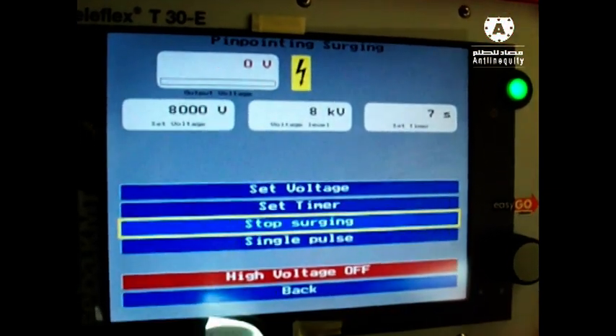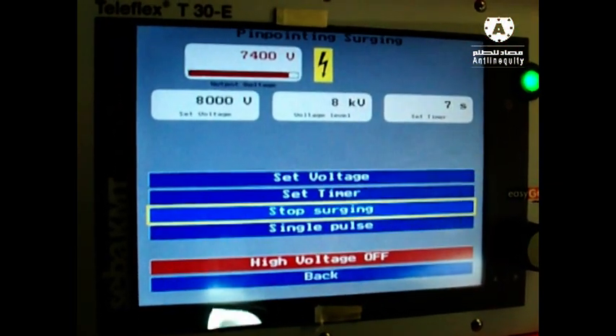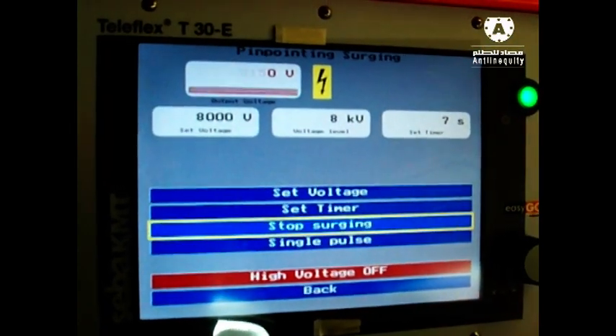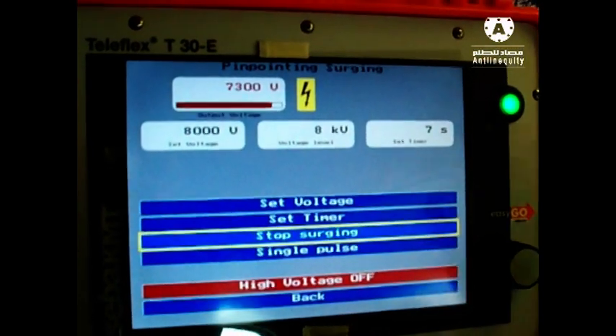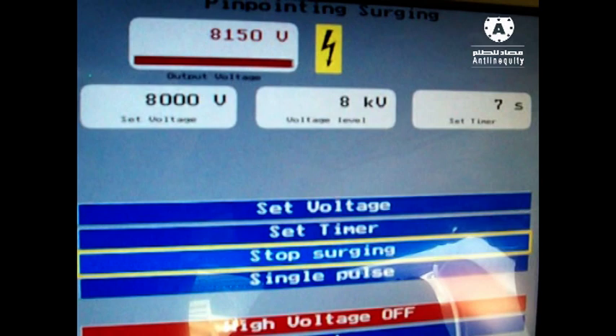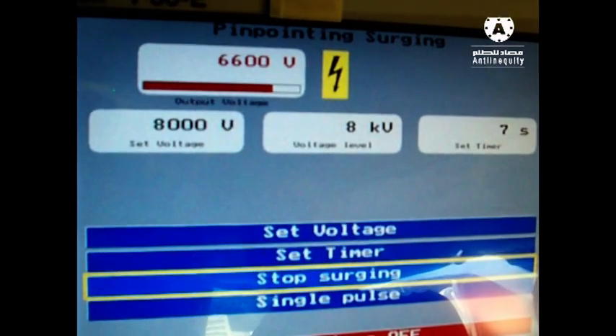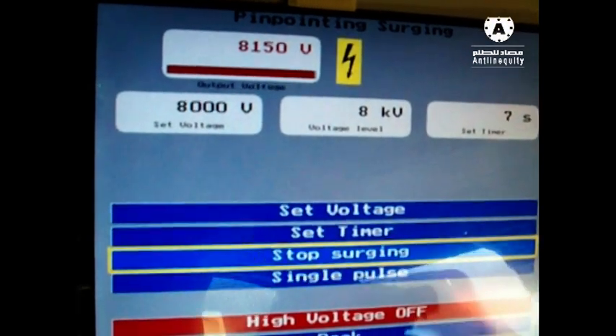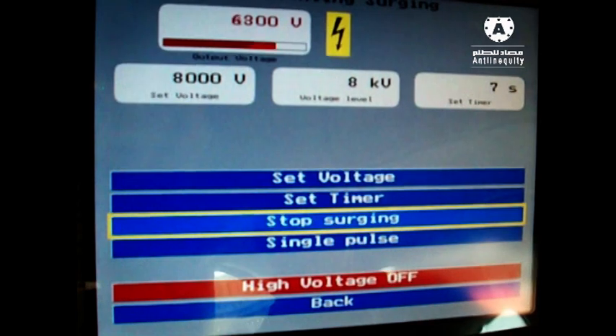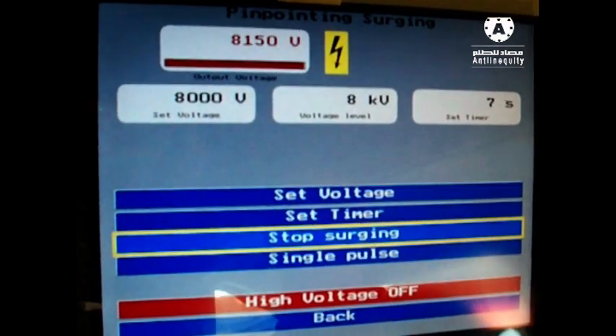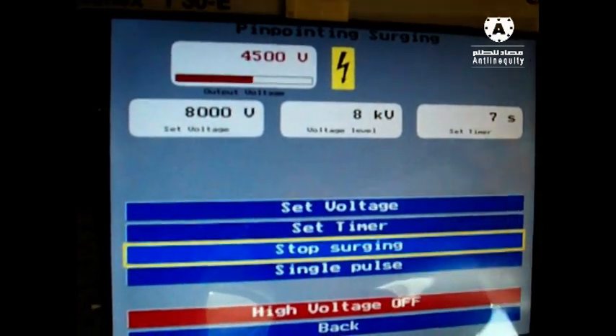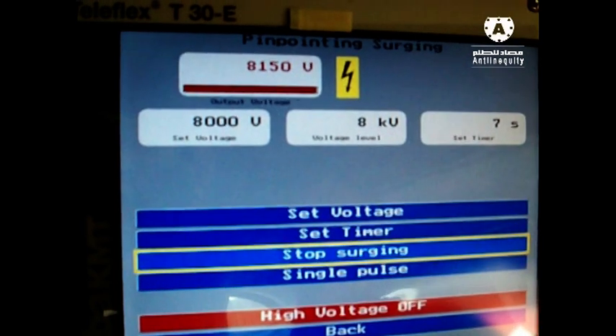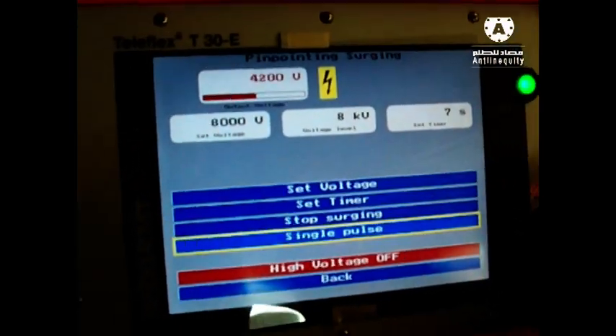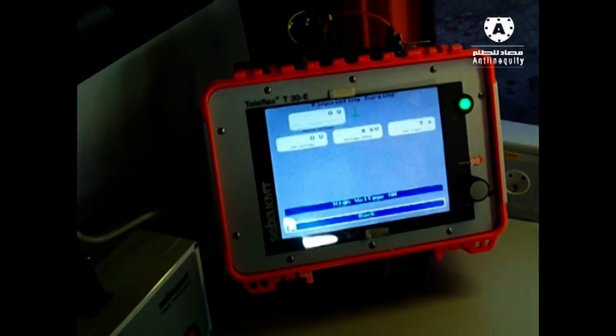Now we have to go out with the digiphone to the point where our TDR or arc reflection mode says that there is our failure, approximately 100 meters, 1 kilometer or more, and a little about 50 meters before our value we should start with our pinpointing, so that we are moving to our fault. Because if we start behind our failure, it's possible that we move away and so we cannot find the fault. Okay, and to switch off the system, switch it off here or directly here. That's it for pre-location and pinpointing.